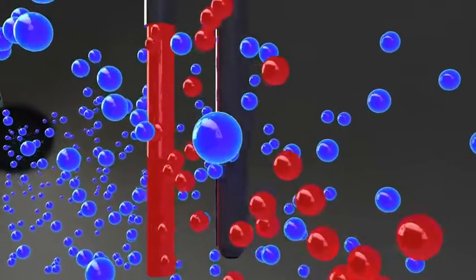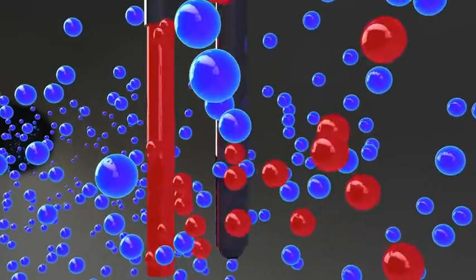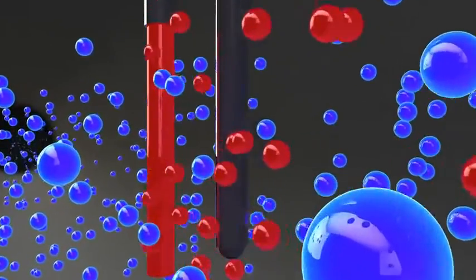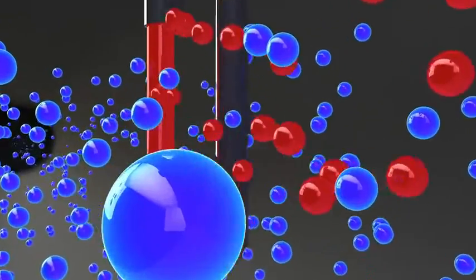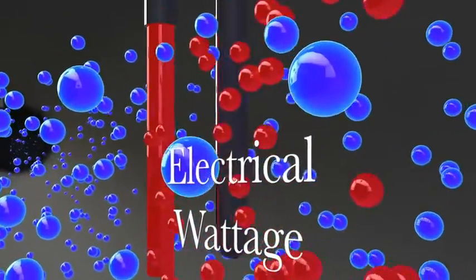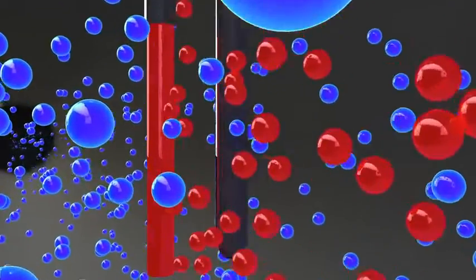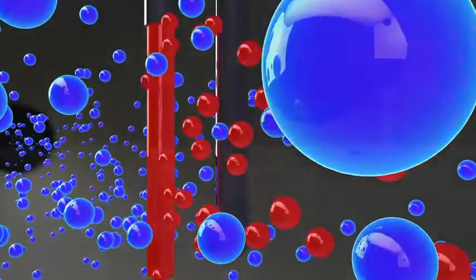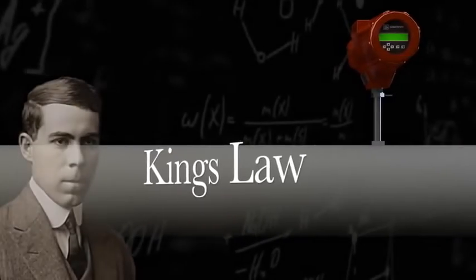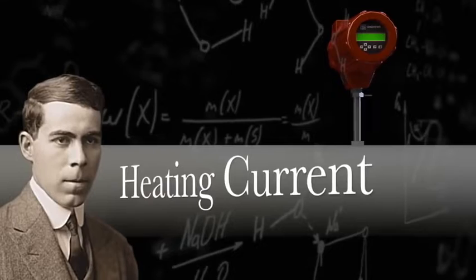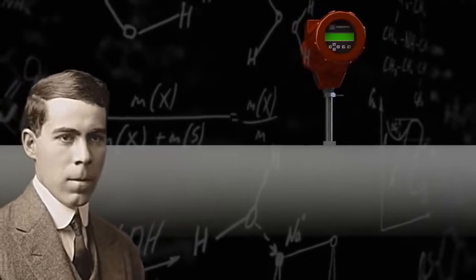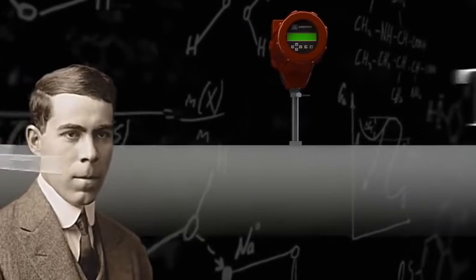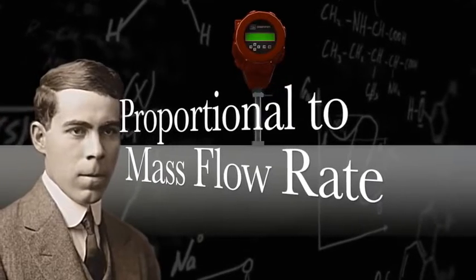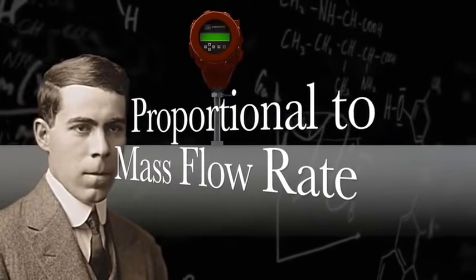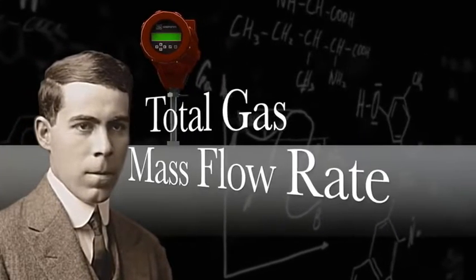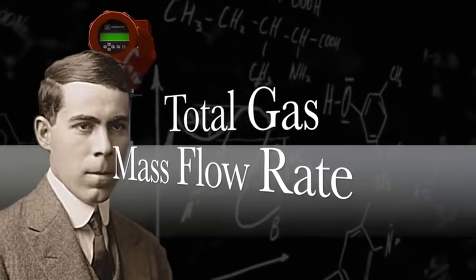So, now that we know the basic measurement principle, how is total mass flow rate of gas flowing through the pipe actually calculated? The meter's basic output is the electrical wattage carried away by the molecular flow. As the mass flow rate increases, the wattage increases. As described by King's law, it turns out that the heating current required to maintain the constant temperature differential between the two sensors is proportional to the cooling effect caused by the gas molecules flowing by, and therefore is a direct measurement of total gas mass flow rate in the pipe.